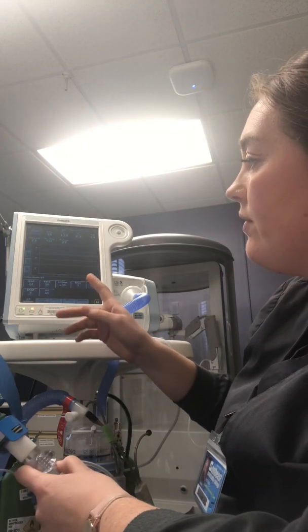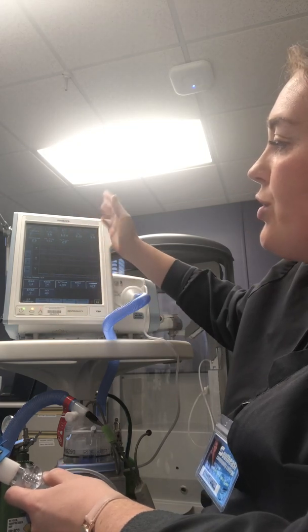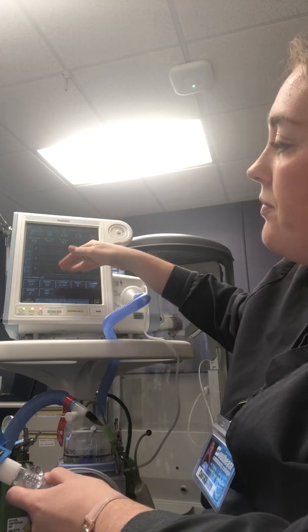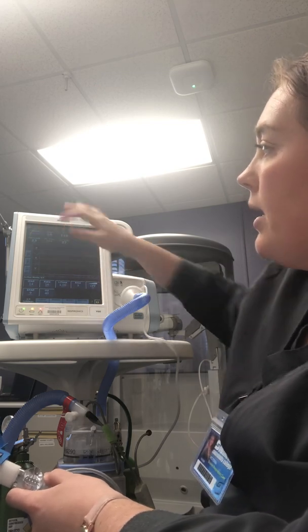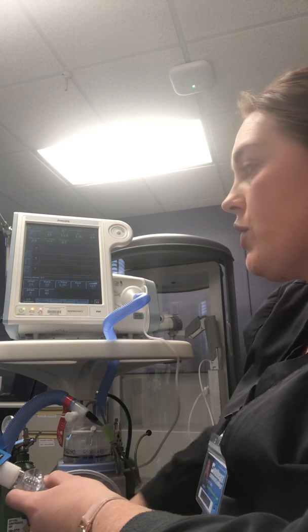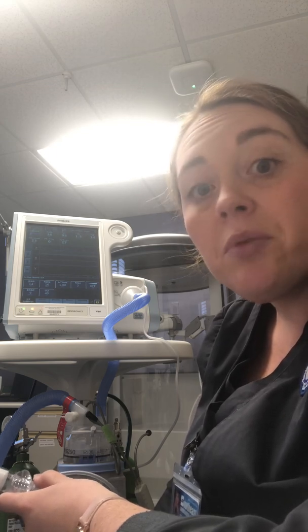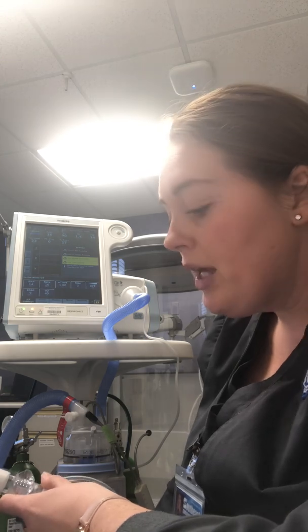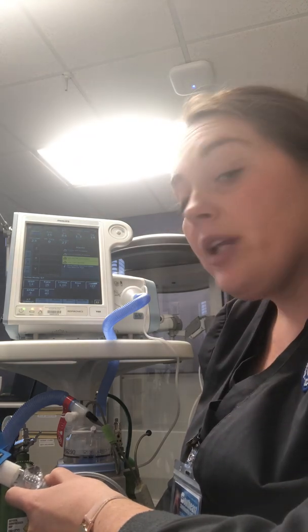Okay, so while looking at the Bipap here, we have all of these settings we can change. We can see that we have our pressure, our minute ventilation, and our volume, which are all being shown across the board here. Then down below is where you can change any of your settings. So regularly IPAP is from 8 to 20 centimeters of water pressure. EPAP is generally 4 to 15 centimeters of water pressure, with a pressure support of at least 4 between the two. Your respiratory rate should be between 8 and 20, and your inspiratory time should be 0.8 to 1.2 seconds. You can have oxygen from room air at 21% all the way up to 100% oxygen.